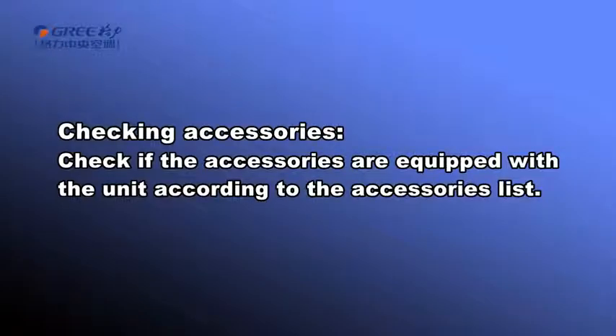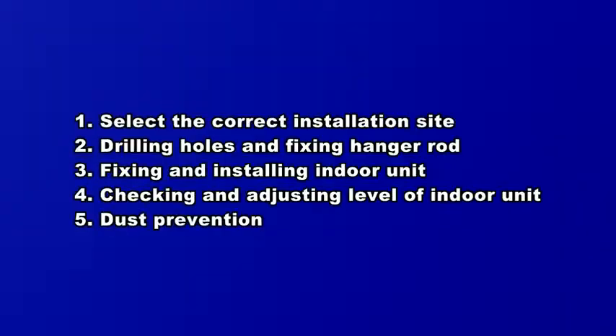Checking accessories. Check if the accessories are equipped with the unit according to the accessory list. Installation of indoor unit. Steps to install the indoor unit. First, select the correct installation site. Second, drilling holes and fixing hanger rod. Third, fixing and installing indoor unit. Fourth, checking and adjusting level of indoor unit. Fifth, dust prevention.